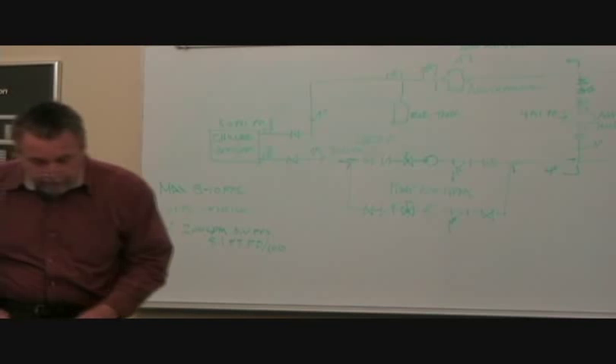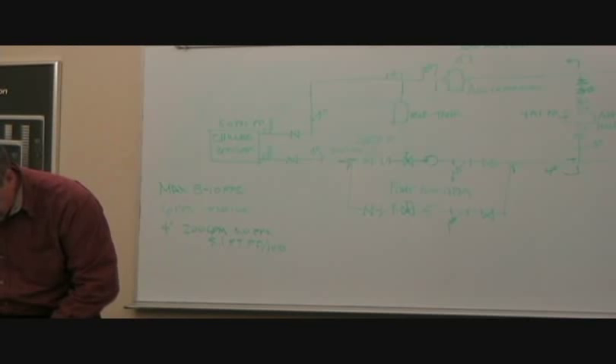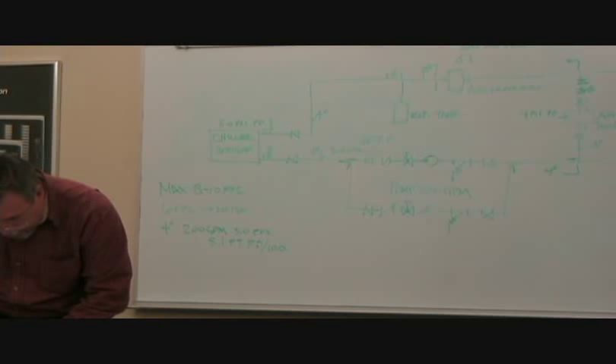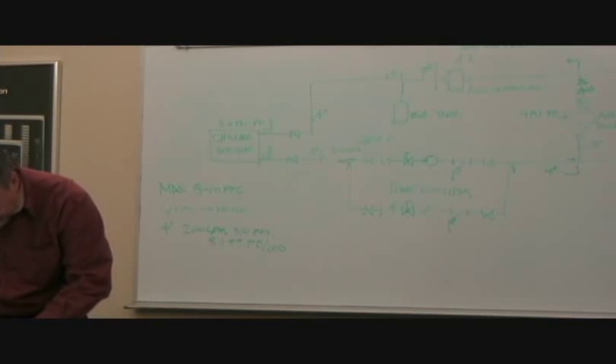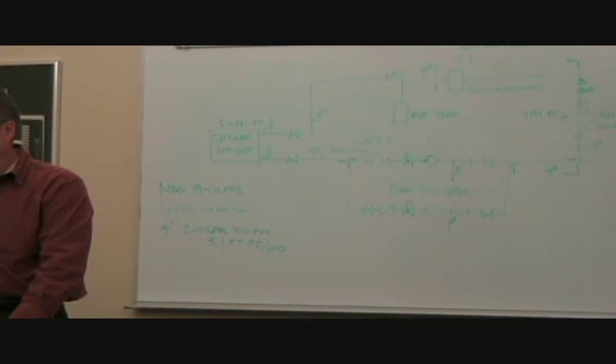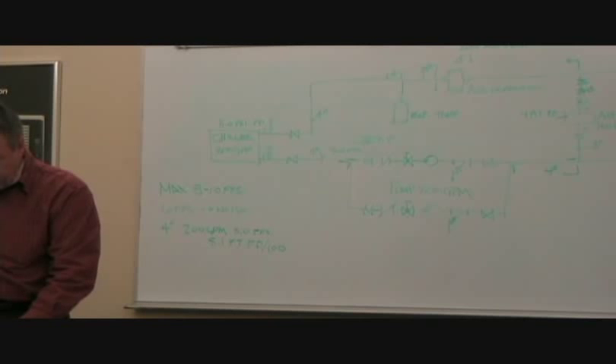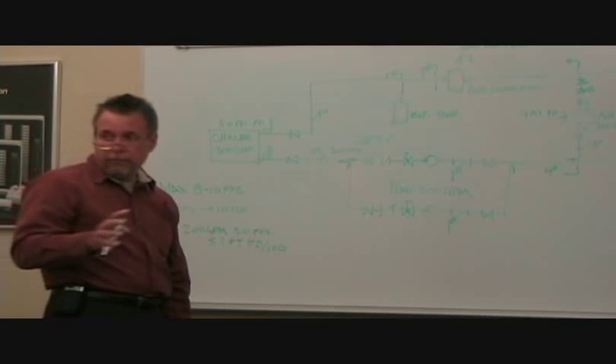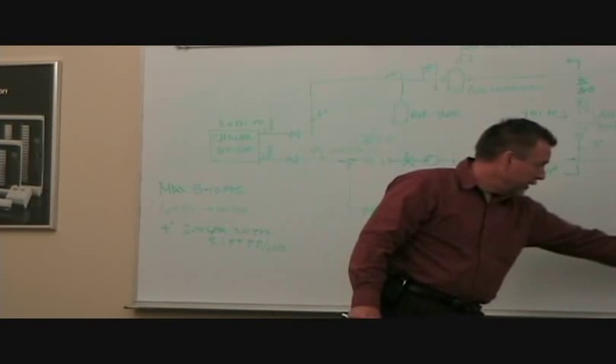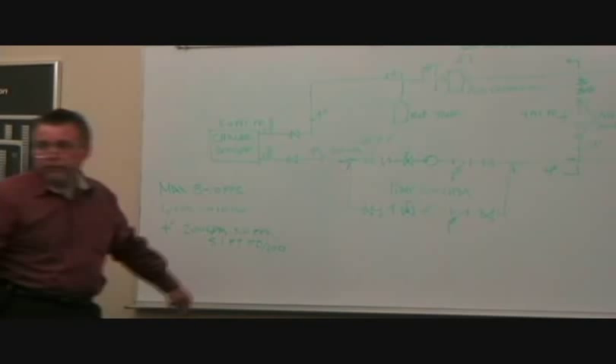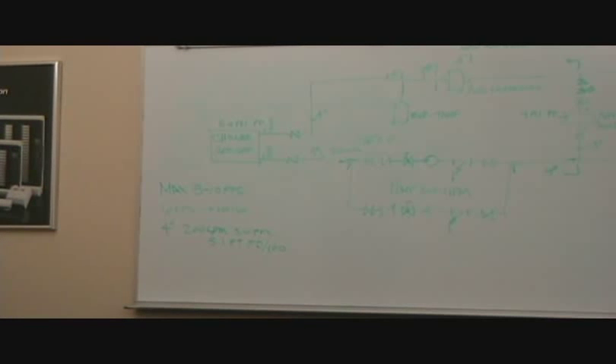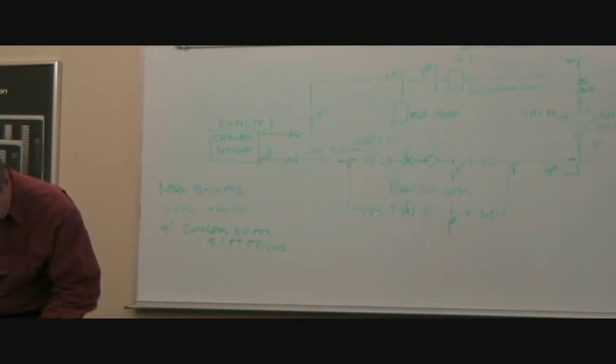So actually what I've done, what the Cameron book tells me, is a very clean pipe. To give you an example, 4-inch pipe, brand new, is 2.25 feet per 100 at 200 gallons a minute. At C130, which is medium roughness, it's 5 feet per 100. So I've actually doubled, because I'm conservative, the amount of loss on the pipe. So that means that it's going to be quieter when it's new.